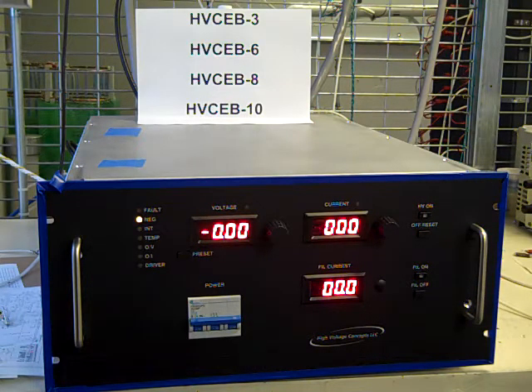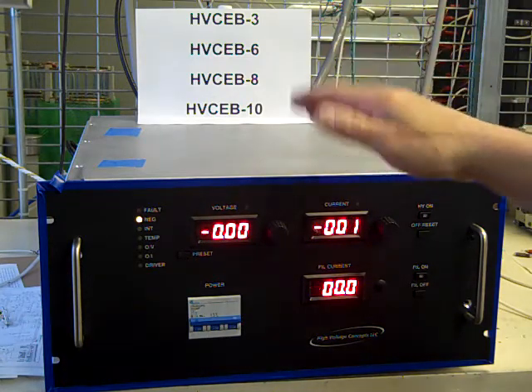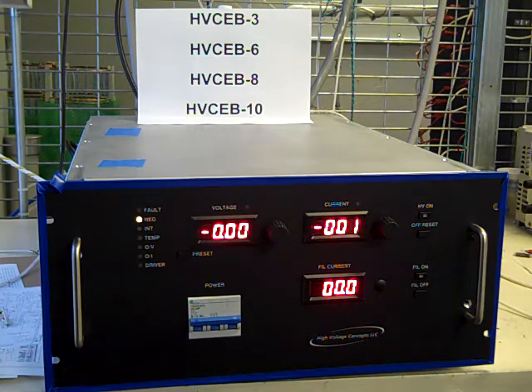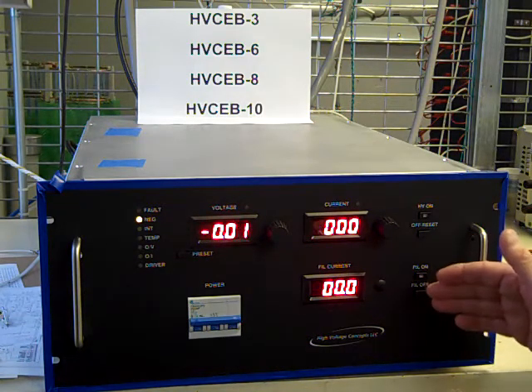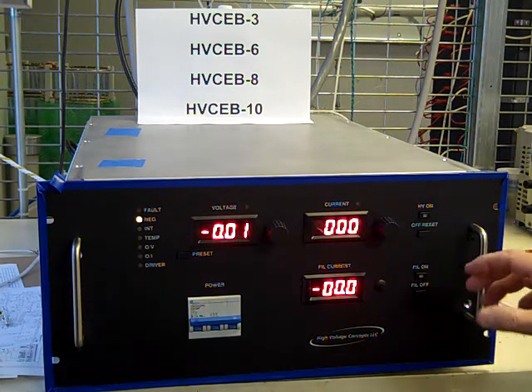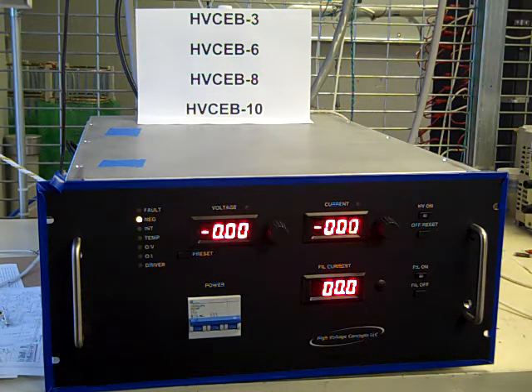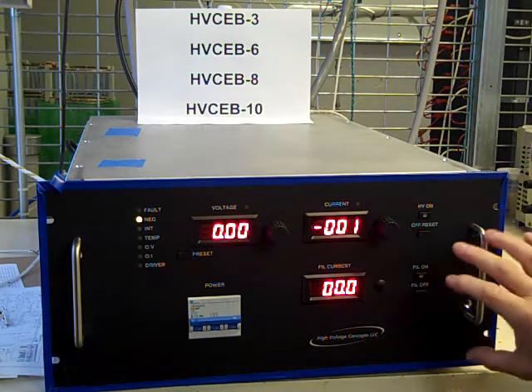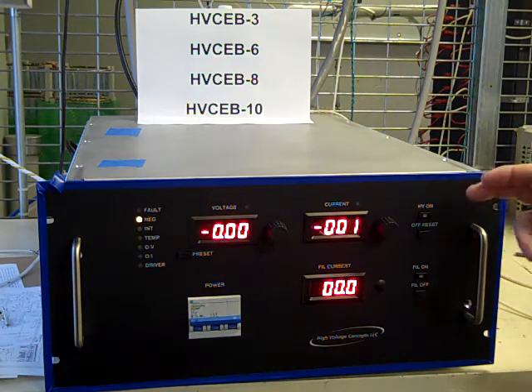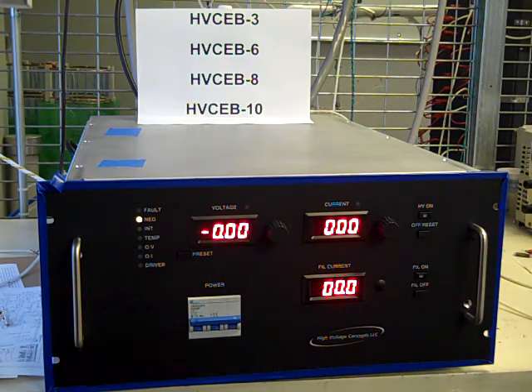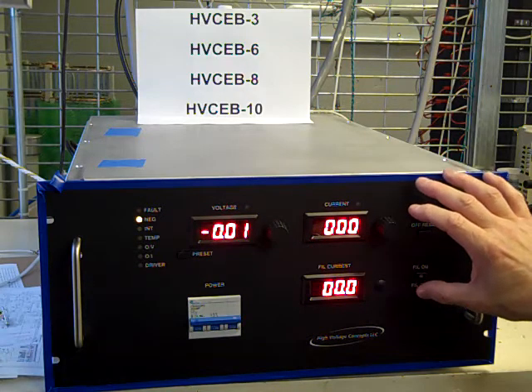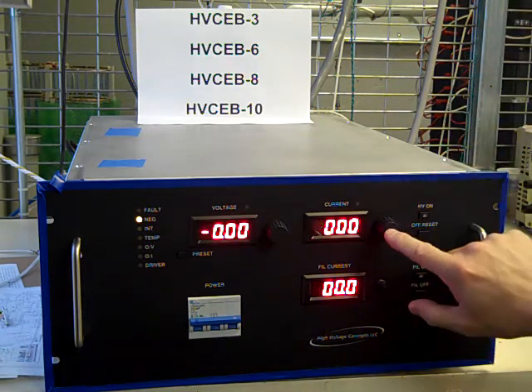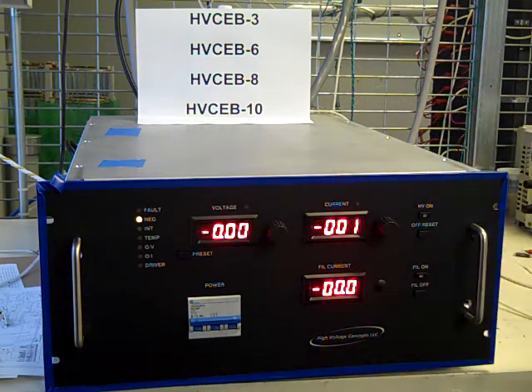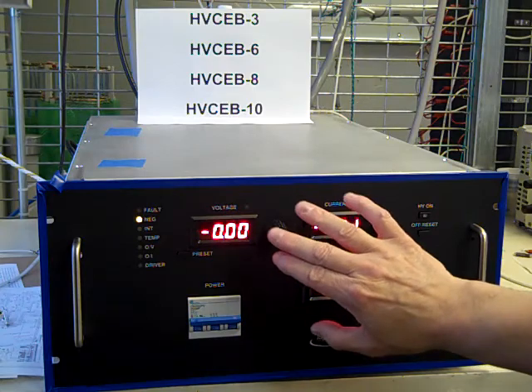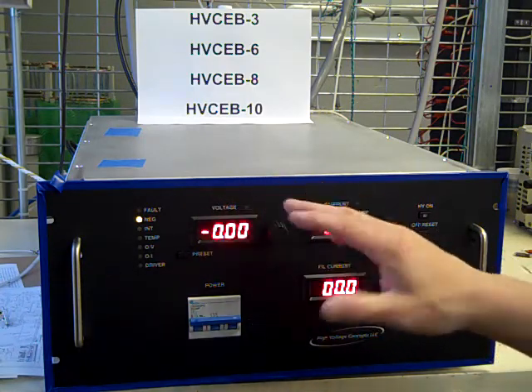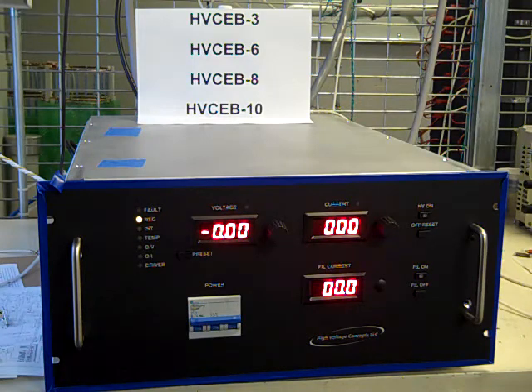Remotely, we're going to put in a 10 to 24 volt signal. After selecting that we want remote, when we put in that signal, the power supply will sequentially turn on by itself as you're demanding high voltage. As long as you're holding that signal to the remote, this power supply will turn on. Once you remove that signal, high voltage goes off first, and then the filament will turn off. The only thing is that when you go into remote, current adjustment is via remote. So the voltage adjustment always stays on the front panel.